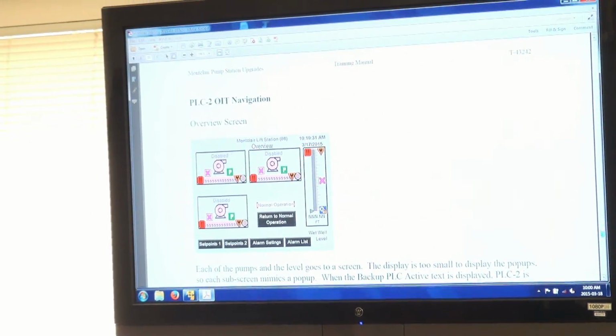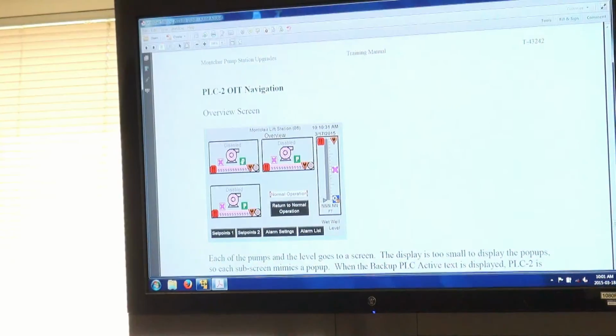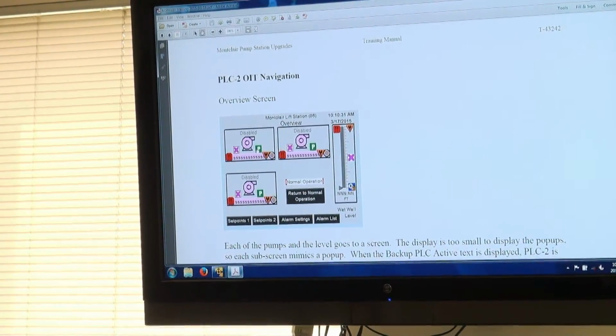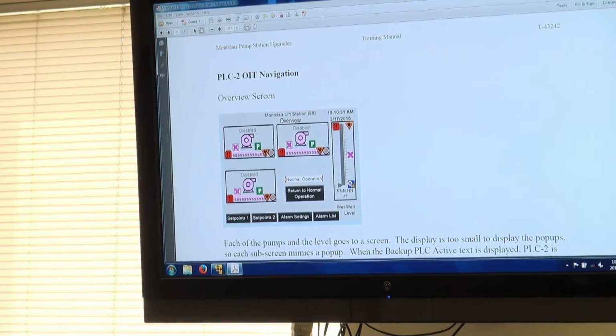I know some sites, the HOA is actually a LOR, local off remote. What does the display look like when somebody goes to the motor control and puts it in local? That would be the yellow H. I think I had that on one of them. Right around this little symbol this P would have a yellow H instead. And that would be what it would be, a yellow H with a black text. Typically, even the program mode doesn't show up. So if you see nothing, you're good. If you see any color up there, other than a blue running, the pump running in blue, and the text saying stopping, then you're normal.